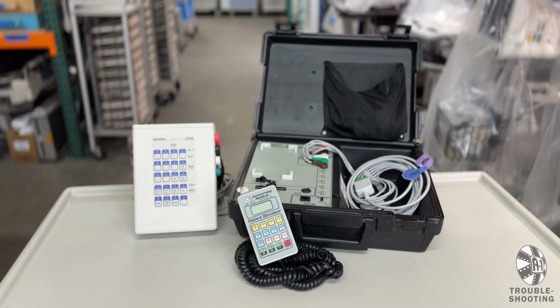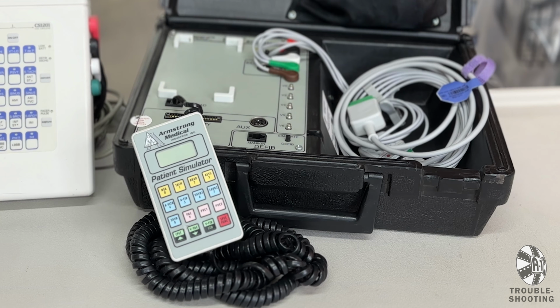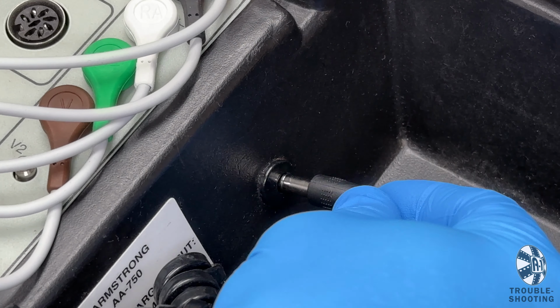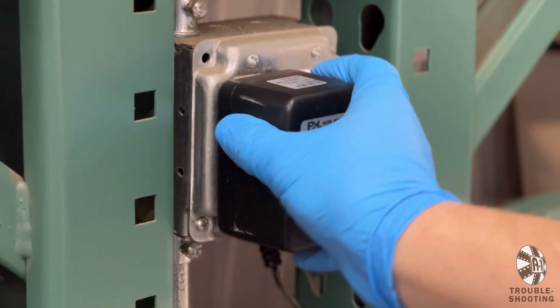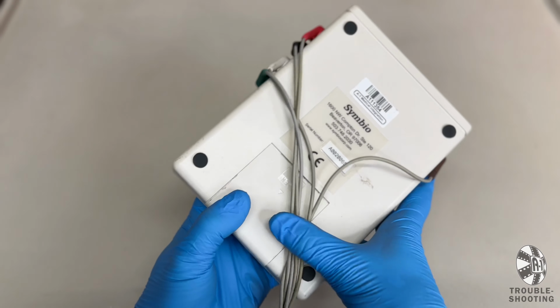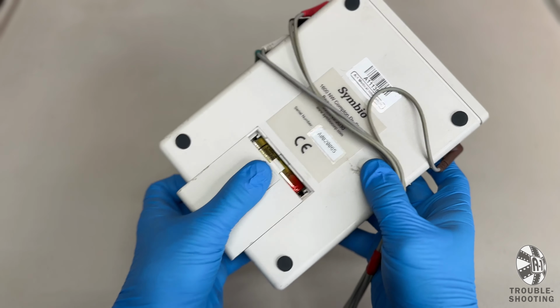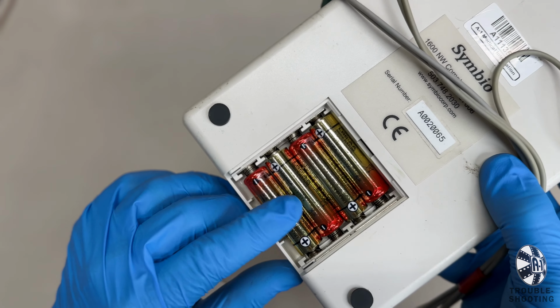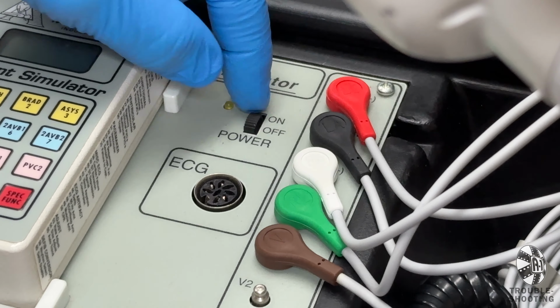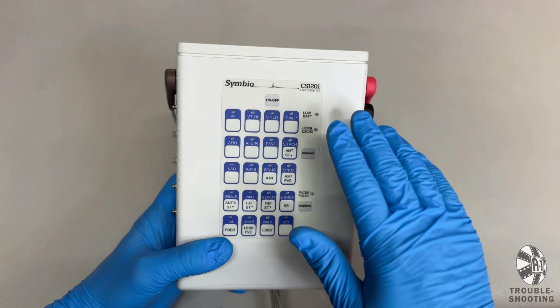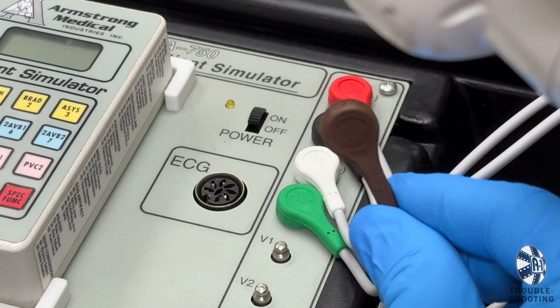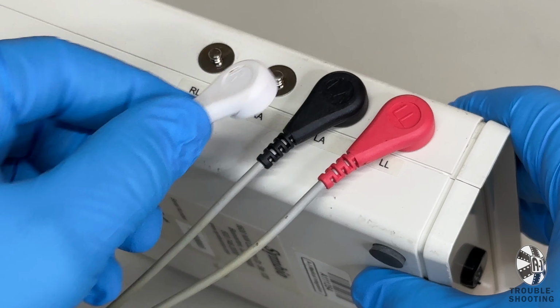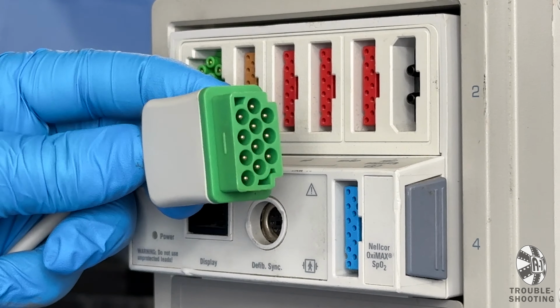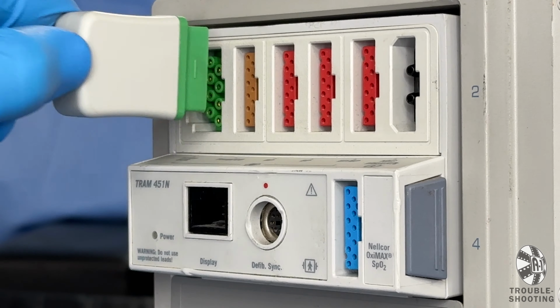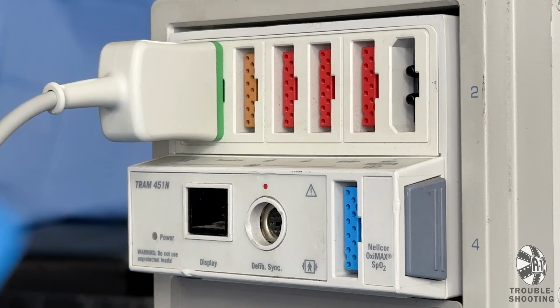The simulator is not working. Make sure it has power. For the suitcase sim, plug it into a wall socket. And for the handheld sim, check the AA batteries to make sure they are inserted and still have power. Cycle the power button. Make sure the 5-lead ECG cables are attached correctly to the sim. Also, check that the green end of the ECG cable is plugged into the monitor interface.